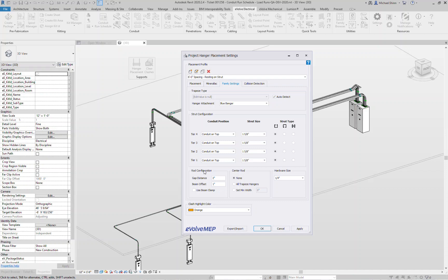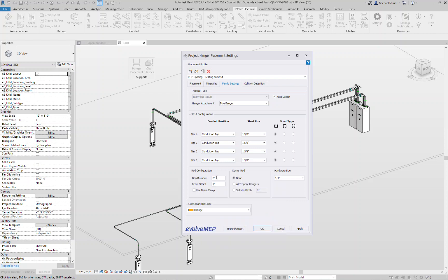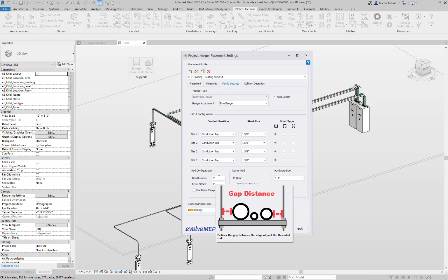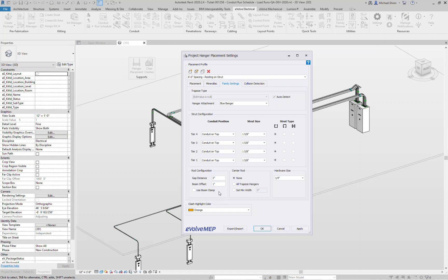Your rod configuration. So your gap distance, where is the outside conduit to that nearest rod, what's that spacing going to be, say two inches. Beam offset, so we are detecting if there's structural framing in the model or in your linked model. So if the rod were to hit an actual beam, what do you want the tool to do? It's going to automatically move the rod over and find the edge of that top of the beam.